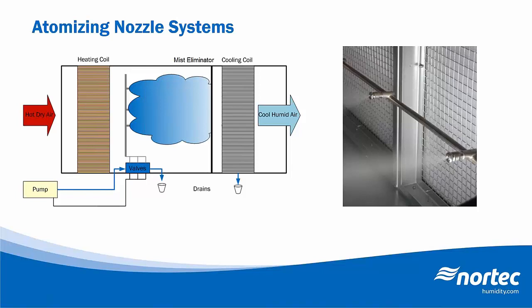Any unevaporated water is typically caught by a droplet separator or mist eliminator that's installed downstream from the nozzle array. The evaporation efficiency will depend on the entering air conditions, so temperature and RH, the air velocity, and the absorption distance, so the distance that we have for spraying that water. So typically with higher velocities or shorter absorption distances, the contact time between the air and the water will be less, so we have less water that can be evaporated.